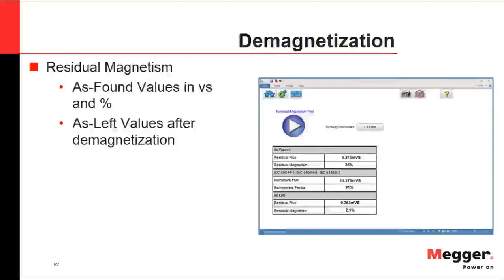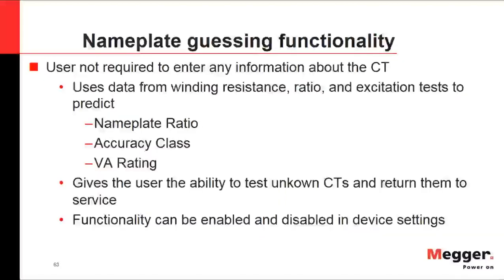Demagnetization in the MRCT also provides 'as-found' and 'as-left' values: before starting the process, you can see how much remnant magnetization exists in the CT core, and after demagnetization, what remnant magnetization remains. This information is provided to the user.